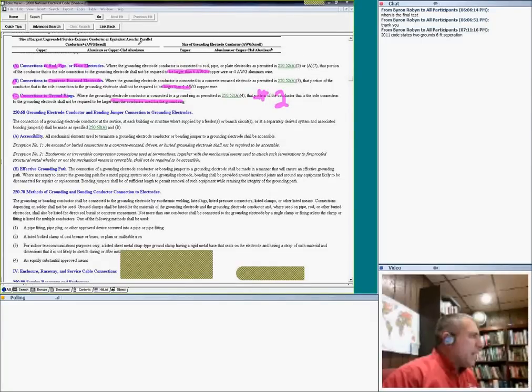If you are tying to a rod, a pipe or plate directly to the rod, you don't have to go higher than number 6. And going to the concrete encased electrode, no higher than number 4. And if you're going to a ring, no higher than number 2. And guys, if you see these and you say, well, why Chad, why aren't they using the table? Because of these exceptions. Because of these exceptions.